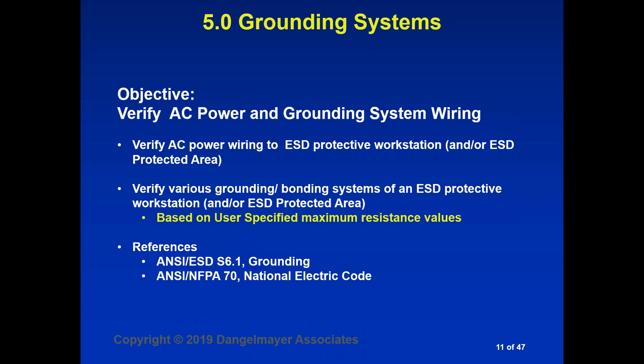The first thing you're going to do is verify your AC power and grounding system wiring, because this is going to be the reference for all of your measurements. So we need to verify the AC power wiring at the ESD protective workstations or elsewhere in the ESD protected area. We need to verify that one of the specified ESD grounding and bonding systems is in use. And for references, we have ESDA standard S6.1, and of course the NFPA National Electrical Code when it comes to grounding wiring.